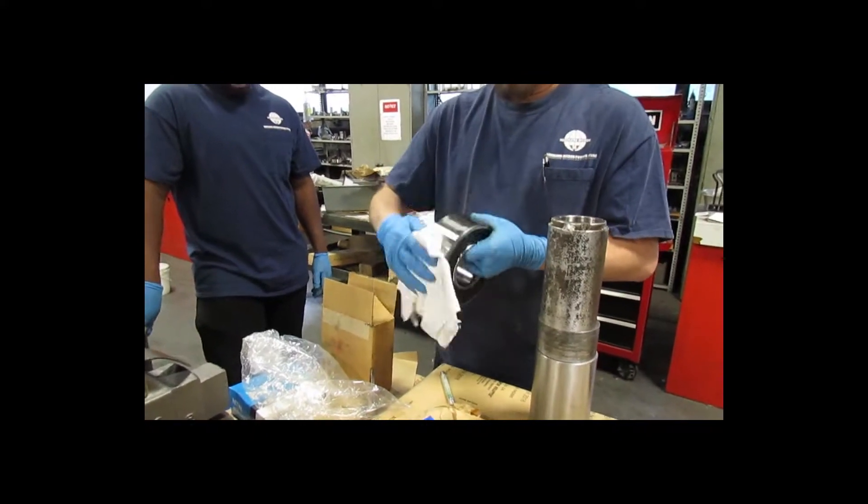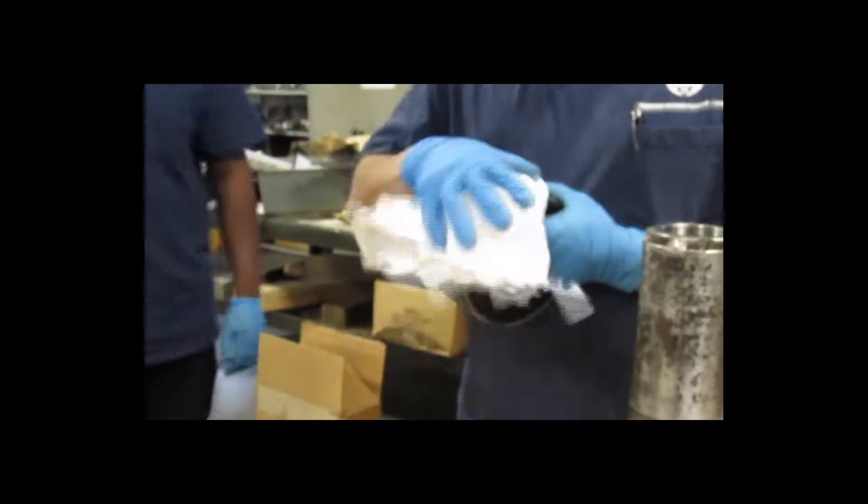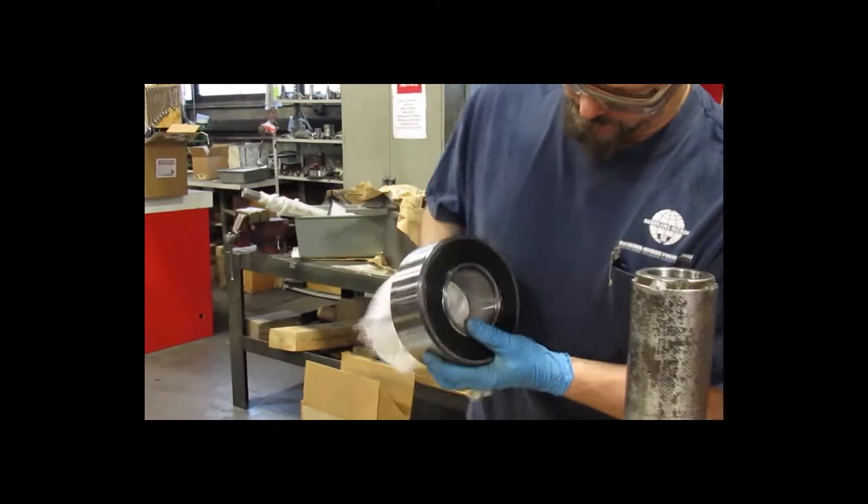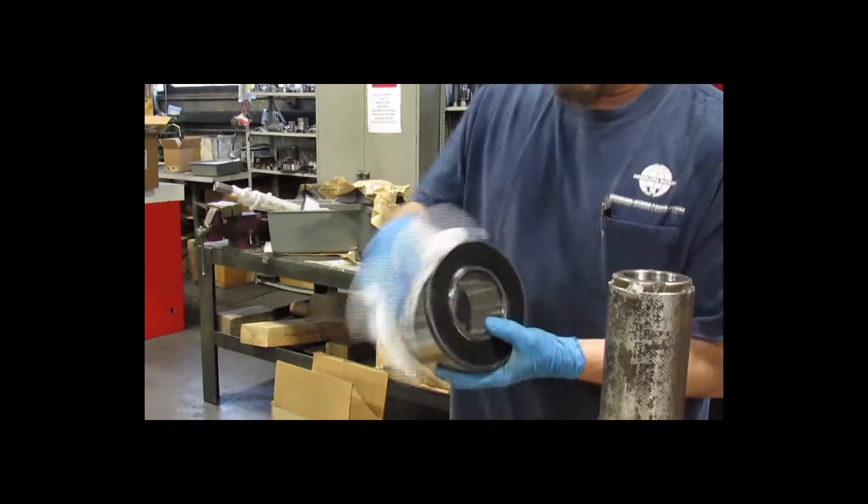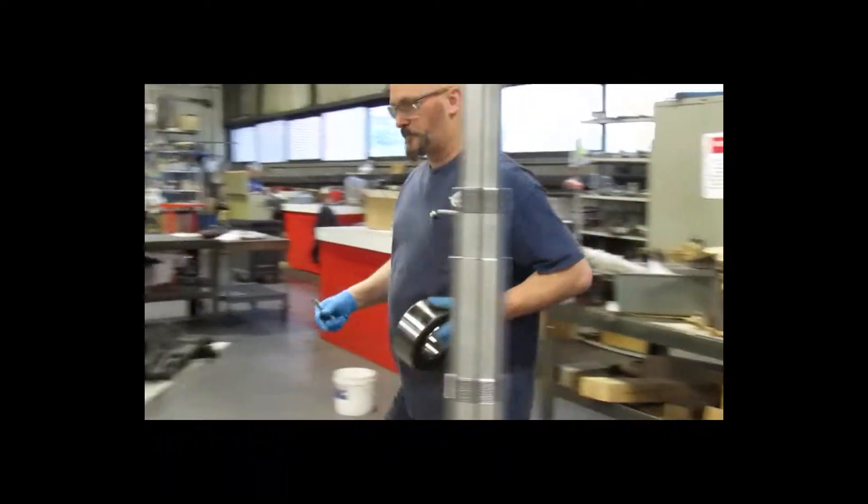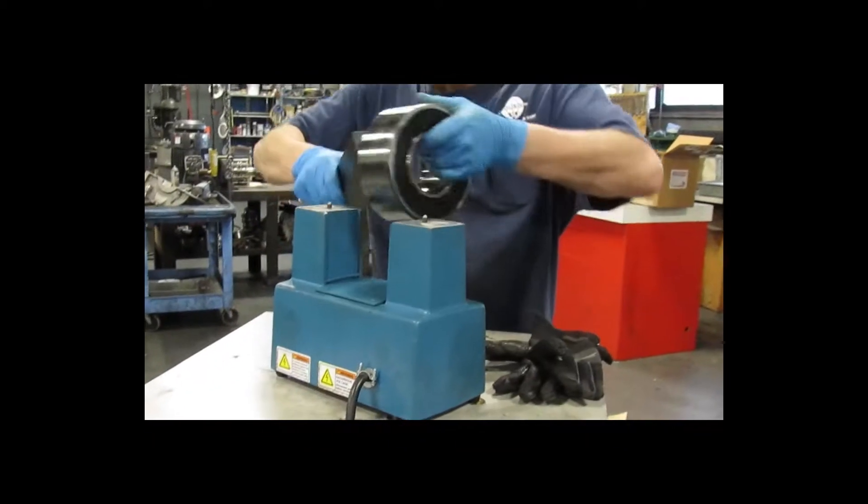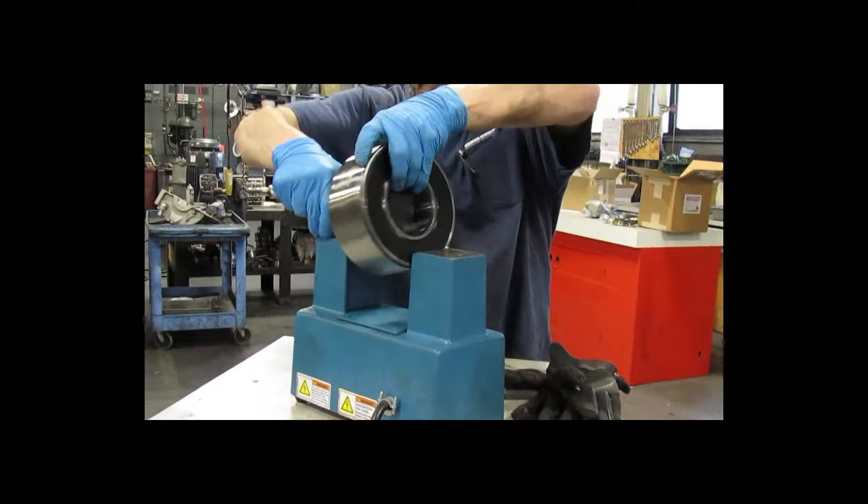When installing bearings, it is always important that when you remove the bearing from its packaging material to clean the bearing thoroughly inside and out to remove any slushing compound or lubricant. When using an induction heater or any type of other bearing heater, it is important to observe the temperature specifications.